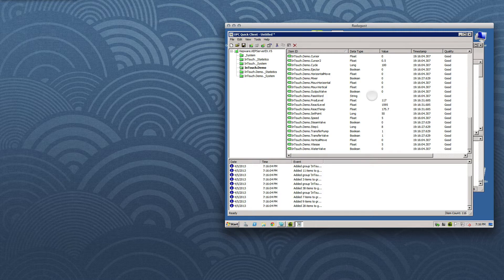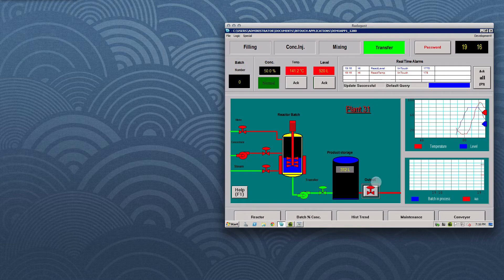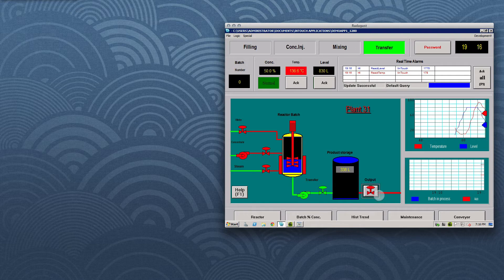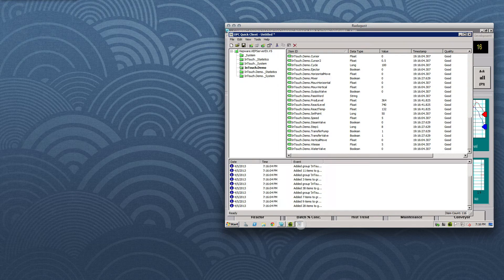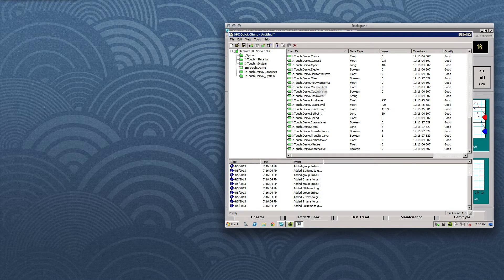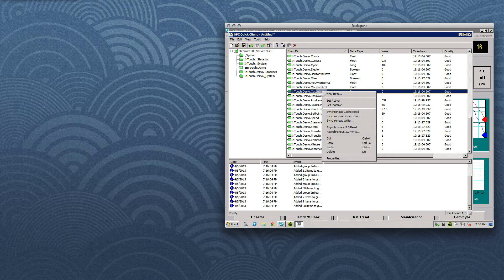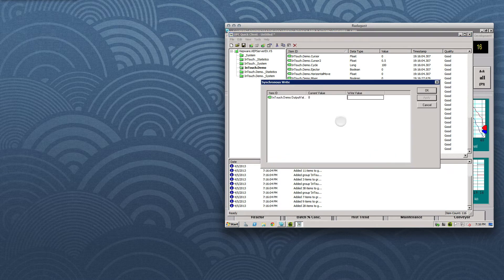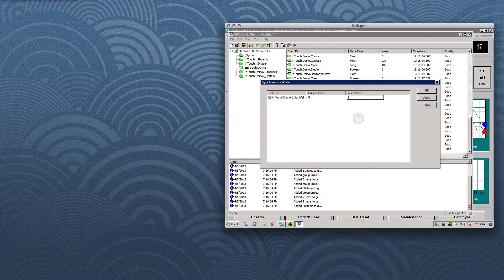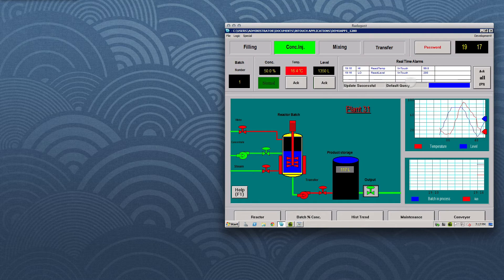Using OPC UA service calls made from the Quick Client, we can also write to InTouch. Here's the output valve in the InTouch HMI, and now let's find the OPC UA node, which corresponds to the output valve in the Quick Client. And there it is. Now, if we right-click, we can call up a menu to let us execute a synchronous write, which corresponds to the write service call in the OPC UA specifications. We'll set the value to 1, or Boolean true, and if we go back to the InTouch HMI, we'll see that that indeed was reflected back into the system.